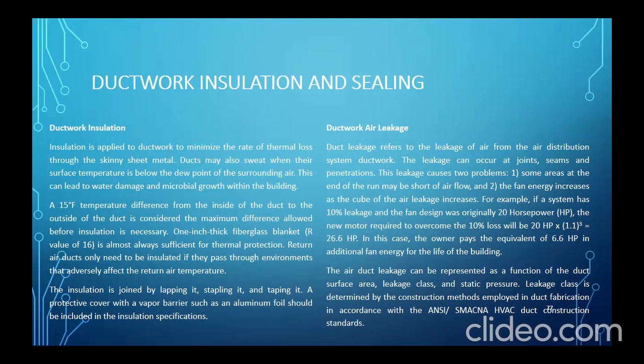Kasi yung flow rate. In this case, the owner pays the equivalent of 6.6 horsepower in additional fan energy for the life of the building. Okay? So the air leakage can be represented as a function of the duct surface area, leakage class, and static pressure. Leakage class is determined by the construction method employed in duct fabrication in accordance with the ANSI/SMACNA HVAC duct construction standards. So doon mo makikita kung ano yung classification ng leakage sa static pressure.